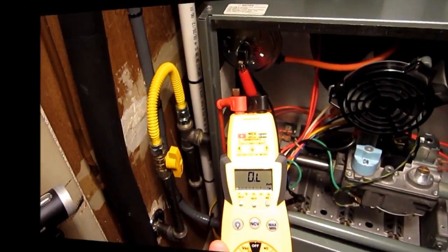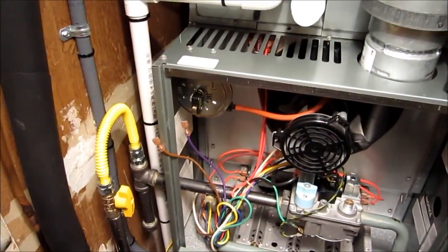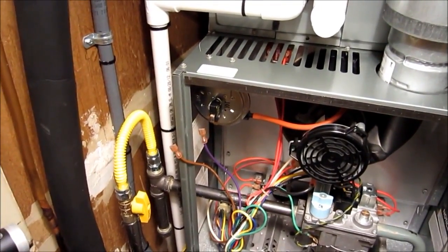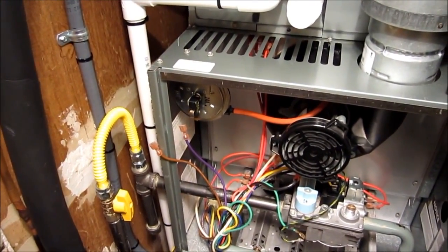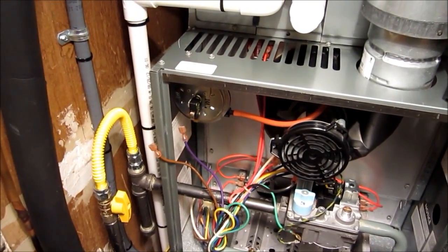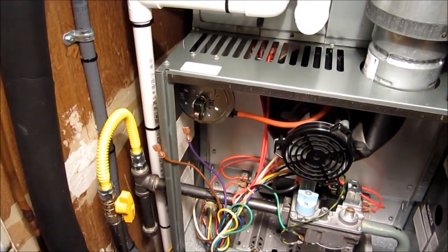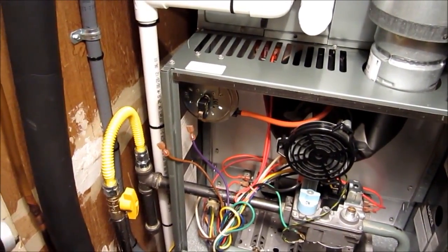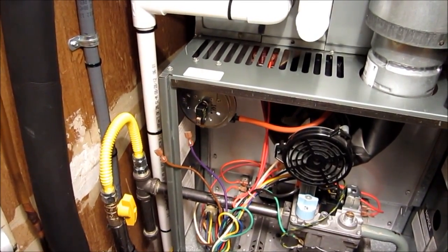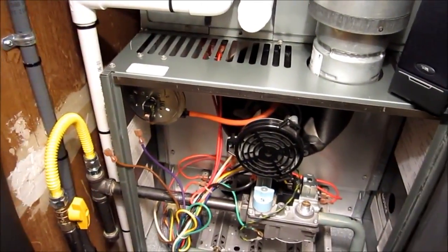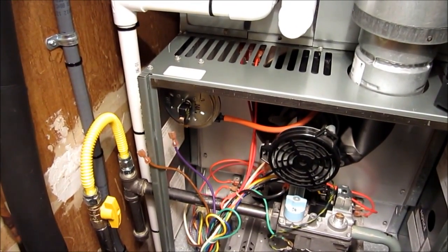Okay Ray, you did a great job on that, man. What we were actually doing with that test before was checking for a shorted pressure switch. This is like the first thing I do when I pull up. So basically, it should read open line, OL is what you see on your digital meter there. If it shows any resistance whatsoever, it's game over. Time to replace the pressure switch.